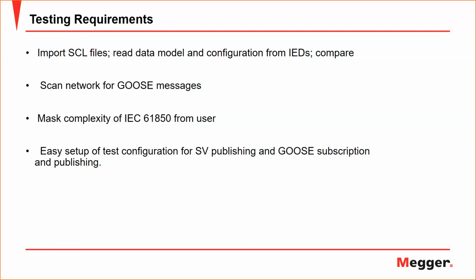I have worked with IEC 61850 for relay protection applications since early 2004, in commissioning, technical support, troubleshooting, and also training. As I said, 2004 is quite many years ago. I'm not part of the IEC 61850 committee, but I'm part of the relay committees in IEC that deal with 61850 for protection applications. So 61850 is not the protection application committee. The protection application committee is called TC95. And in TC95, we are dealing with a technical report that says how to make a relay, how to test a relay, how to specify the relay performances when 61850 is used. So it says how to use 61850 for relay protection applications.